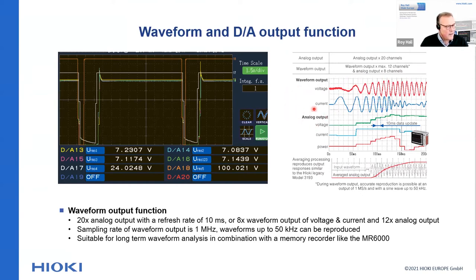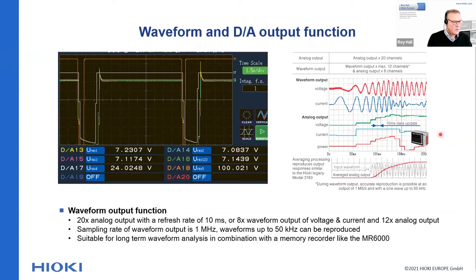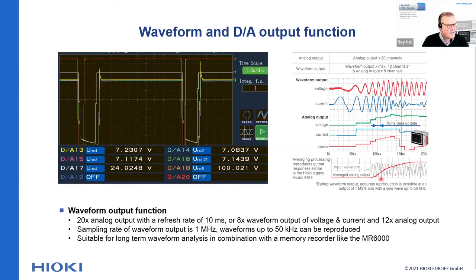The waveform output can be combined with an analog output, which is essentially a trend of the measured RMS values. The update interval is the same as the display update interval, at a minimum of 10 milliseconds. When you are interested in long-term characteristics of your system, you can connect these signals to a high-performance memory recorder such as the Hioki MR6000, enabling long-term saving of voltage and current values and waveforms for later analysis.